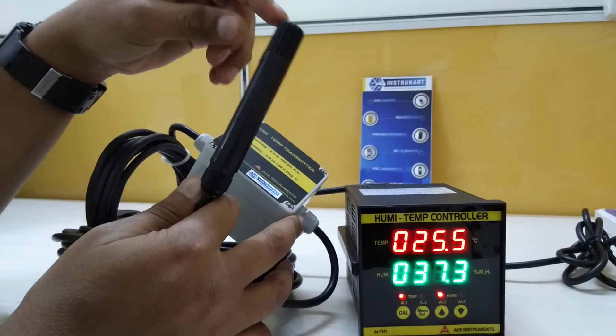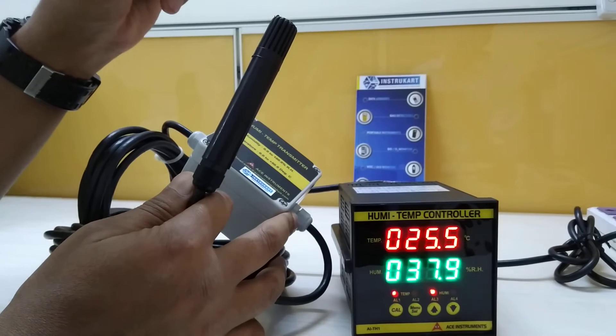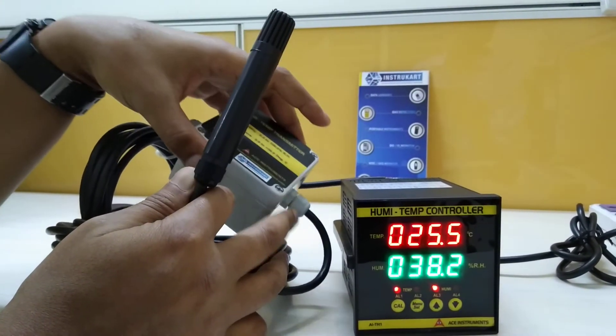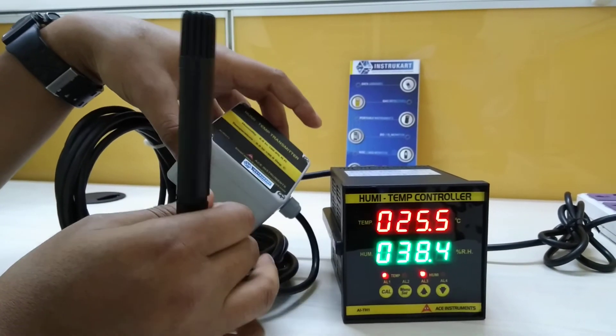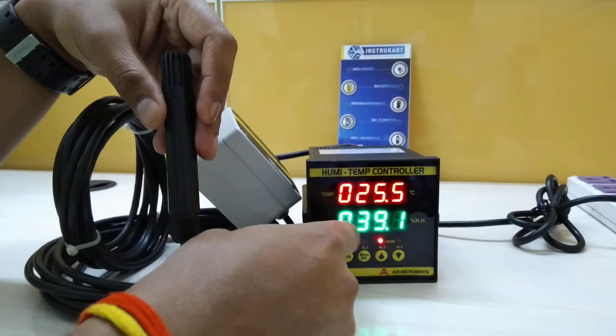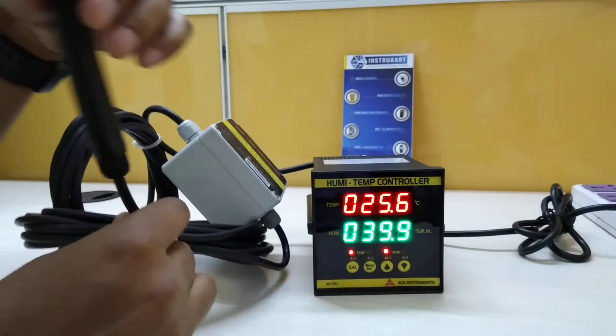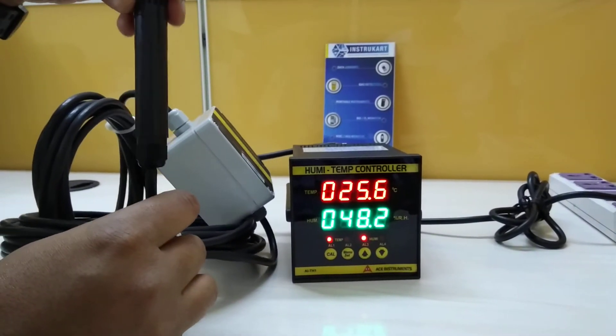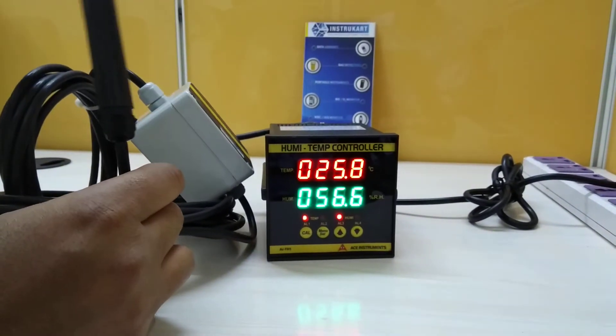The accuracy for this would be 1.8% for humidity and 0.5 degrees Celsius for temperature. You can see that the indicator LEDs are glowing, which means there are some set points that have been triggered. You can see the change in temperature and humidity if we blow onto the sensor.